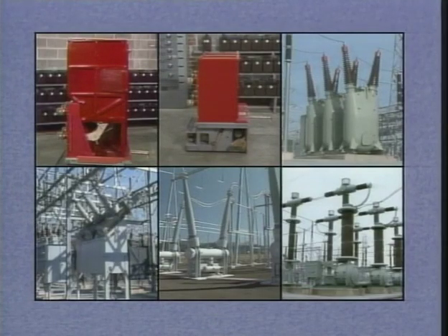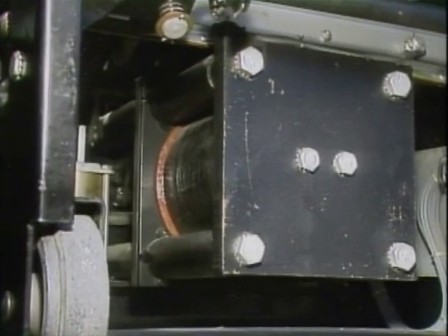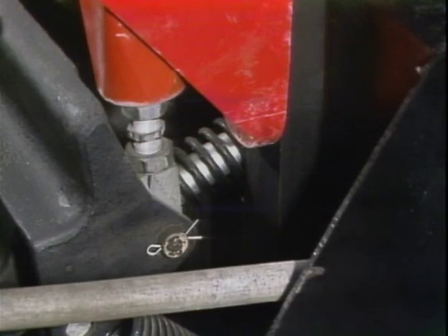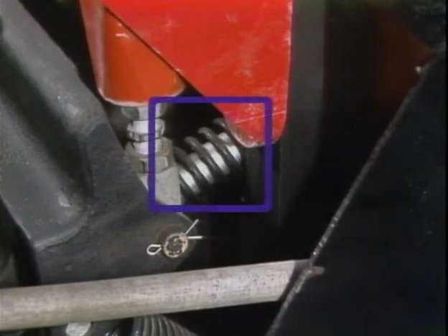Each of the 6 types of circuit breakers is operated by one of 4 basic types of circuit breaker operating mechanisms, or variations of the 4 types. One of these is the solenoid operating mechanism. In the solenoid operating mechanism, a solenoid coil provides the force needed to close the breaker's contacts and at the same time compress an opening spring. The compressed opening spring provides the force needed to open the breaker contacts.